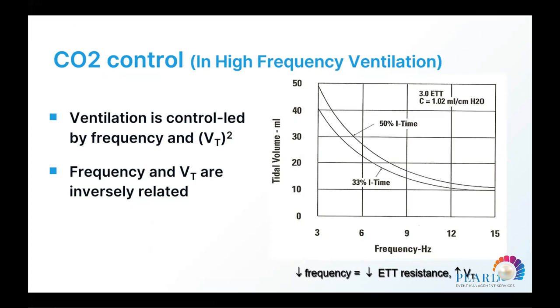I'll give you an example of this. When we use 1:1 or 1:2, the frequency, first of all, is inversely related to the tidal volume. And this is not because of the I time and E time. If you ask the manufacturer, they will tell you this is really not I time and E time. This is just the airway resistance part. When you go up on the rate in high frequency, you're creating more resistance to air movement in the airway, and you decrease your tidal volume. And the more you do it, the less tidal volume you get with a 1-to-2 ratio than with a 1-to-1 ratio. So if you really want to ventilate babies on a newer ventilator, you have to put them on a 1-to-1 ratio. When they get better, you put them on a 1-to-2 ratio.